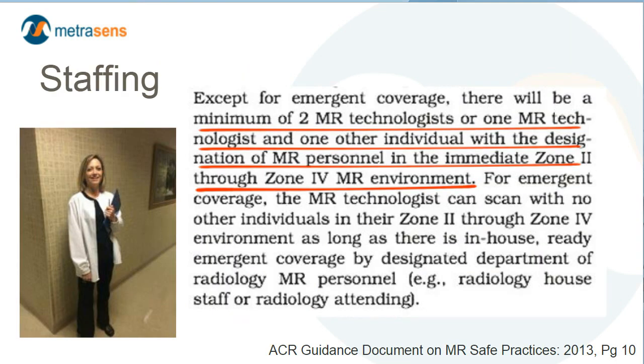The ACR guidance document on MR-safe practices addresses MR staffing. On page 10, the ACR states that except for emergent coverage, there will be a minimum of two MR technologists, or one MR technologist and one other individual with the designation of MR personnel — meaning Level 1 or Level 2 training — in the immediate Zone 2 through Zone 4 MR environment. One staffing model utilized by several clients is the use of MR tech aids. MR tech aids can be highly trained to perform all MR functions with the exception of screening, including turning the room around, screening patients, and positioning patients. Using a staffing model of MR tech and tech aid is a viable option for many facilities.